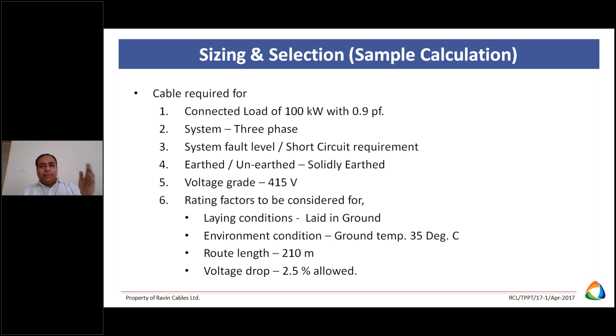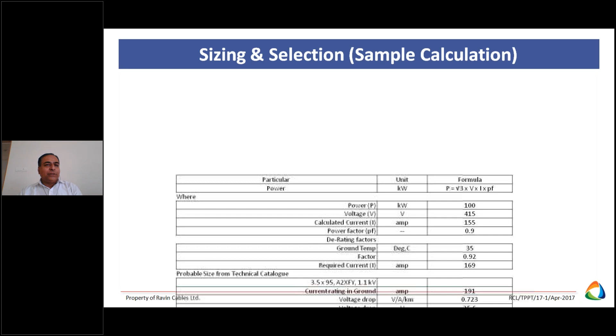Then how do we calculate? Ultimately, power is voltage into current into power factor. So that simple formula we applied here. Here particulars are there, unit is there, formula is defined. Power equals root 3 into voltage into current into power factor. Requirement is 100 kilowatt, voltage 415. Simply we put values and we find current is 155 ampere. Then power factor is 0.9 here.